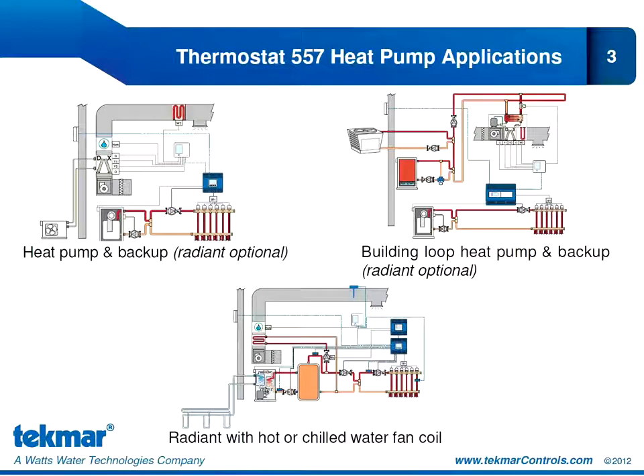These are the primary heat pump applications for the 557. The first application in the upper left-hand corner shows an air-to-air heat pump that is providing forced air heating and cooling to the building. We also have the option shown of adding a radiant floor to this system. If we do that, then the radiant would be our first stage of heat. Our heat pump could provide a second and a third stage of heat if it's a 2-stage heat pump. And we also have the option of a 4th stage of heat by enabling a backup electric strip through the W2 relay connection. In cooling mode, we can provide up to 2 stages of cooling if we have a 2-stage heat pump. So this system is a 4-stage heat and 2-stage cool heat pump application.